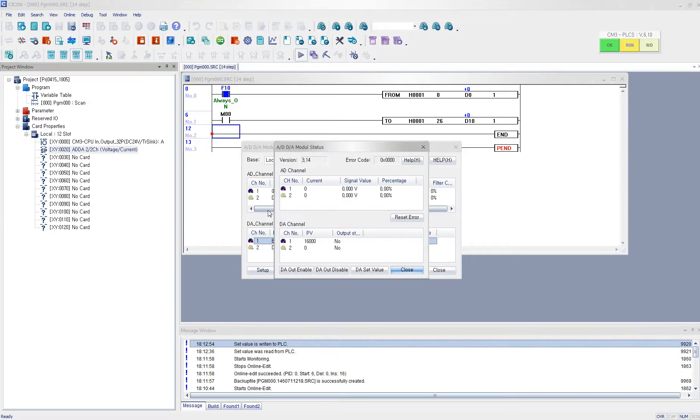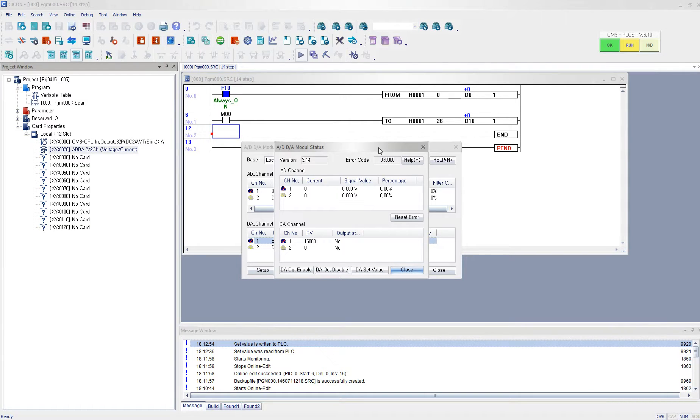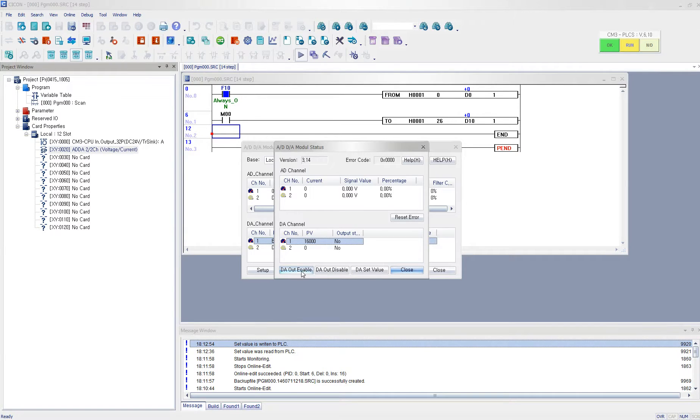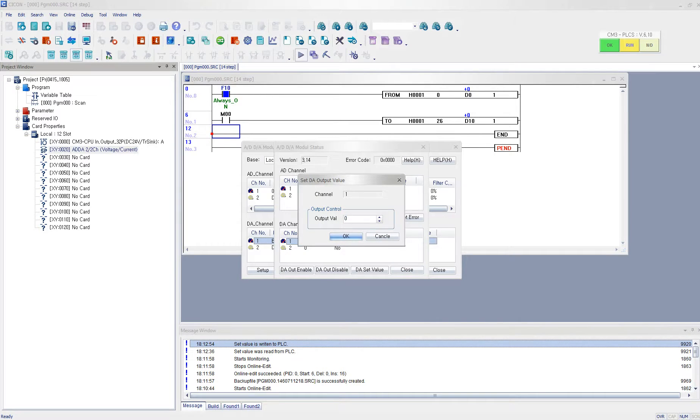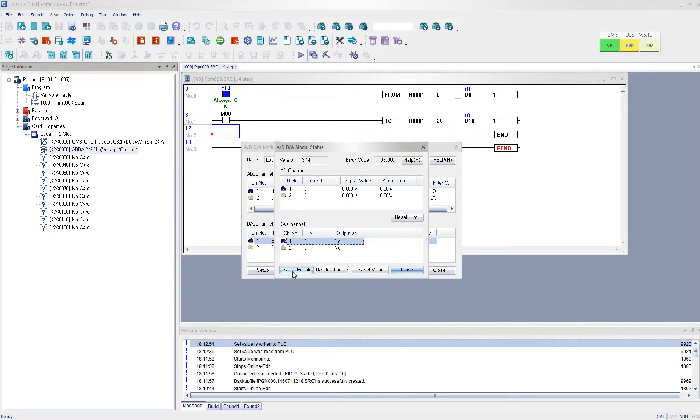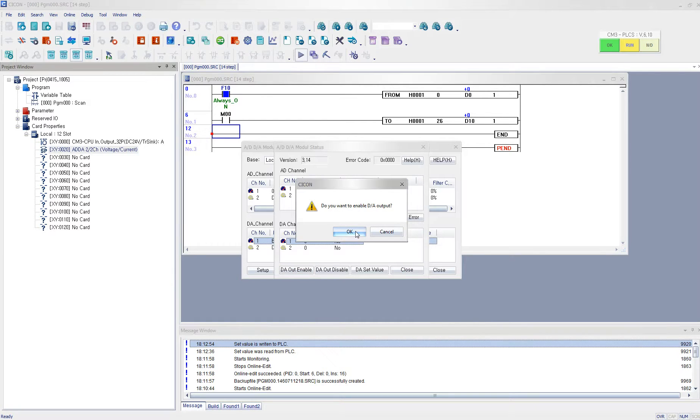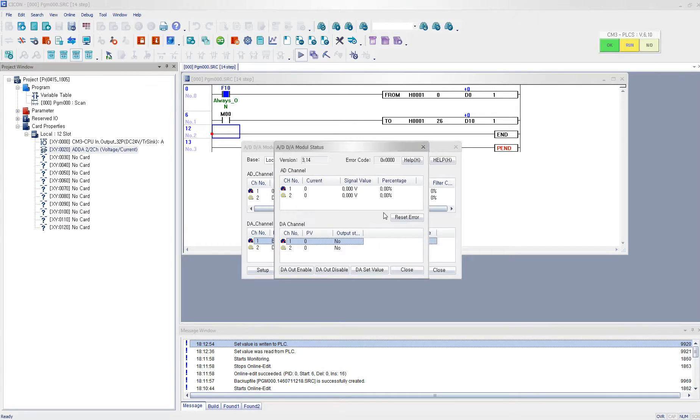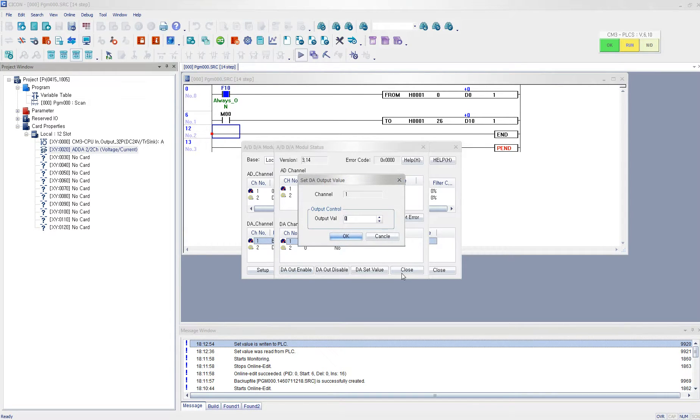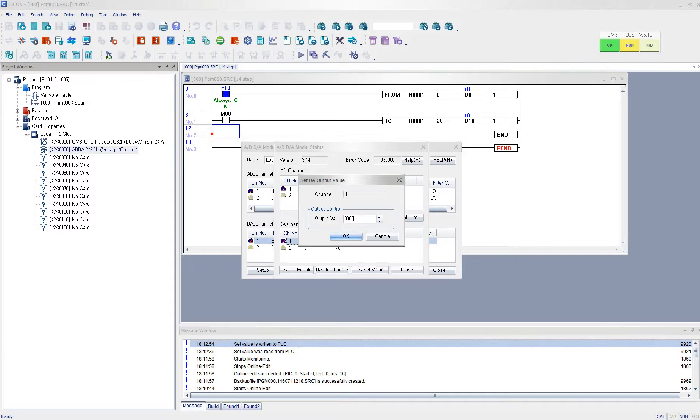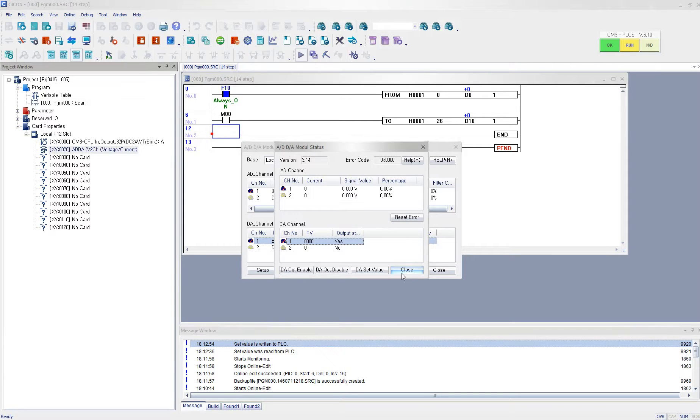And I'm using my calibrator. Here, I'm going to measure the voltage. So if I select enable digital DA output, then it will enable the output value. And let's say if I enter 8000, then it is supposed to output 5 voltage. And my calibrator should read 5 voltage, and it is reading 5 voltage.